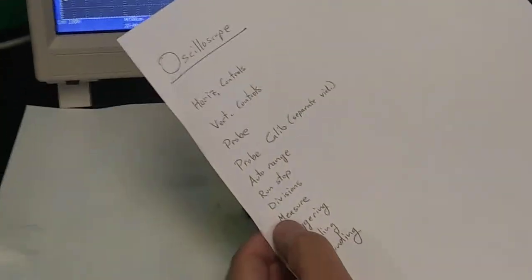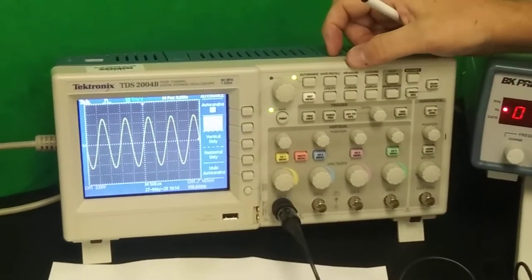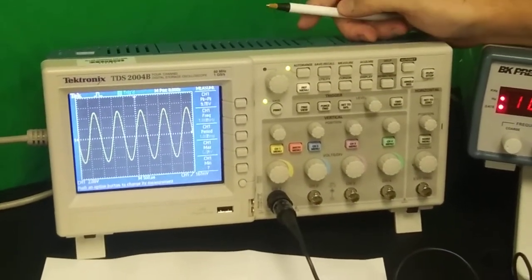So if you get a signal that's floating all over the screen, sometimes you may need to hit run stop and that pauses things and takes a screen capture at one split second in time and that can help you read a messy signal. Usually that's caused by bad triggering. Alright, so now it's going again. We've talked about divisions.